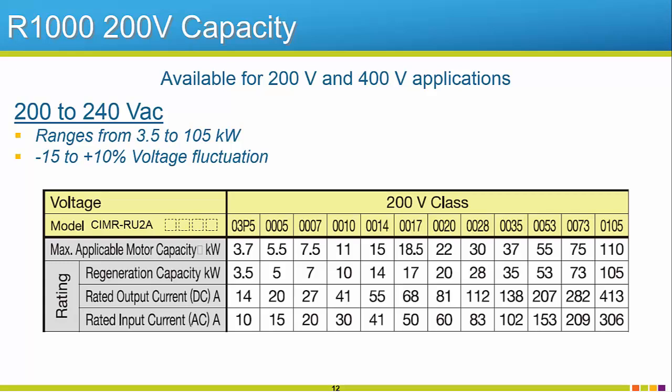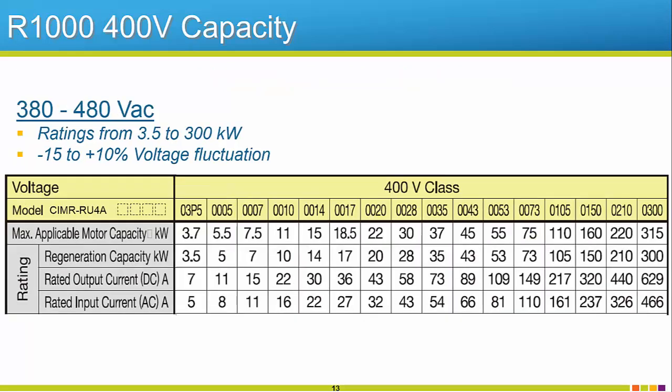The R1000 will be released for both 200 volt and 400 volt supplies. The 200 volt class is rated for 200 to 240 volts AC. The ranges vary from 3.5 kilowatts up to 105 kilowatts. A maximum voltage deviance of minus 15% to plus 10% is allowed. For the 400 volt class, this allows for a 380 volt input all the way up to 480 volts max. This class features a broad spectrum and capacities varying from 3.5 kilowatts to 300 kilowatts. The same minus 15% to plus 10% voltage tolerance exists.